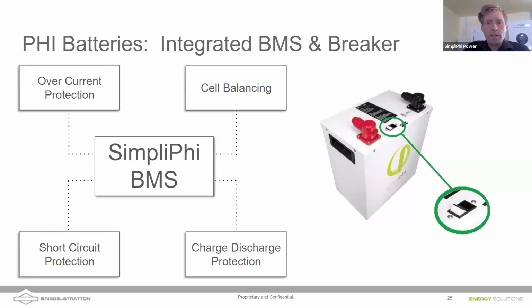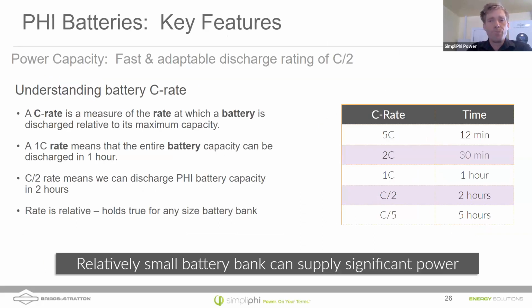This is our SimpliPHI. The SimpliPHI BMS is inside the battery to protect for overcurrent. It's there for cell balancing, to make sure all those cells stay balanced with each other so that you maintain that optimal capacity. And it's also there for short circuit protection. We've got a built-in breaker on that battery, an 80 amp breaker.